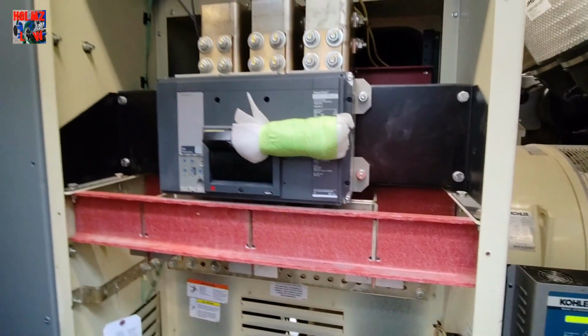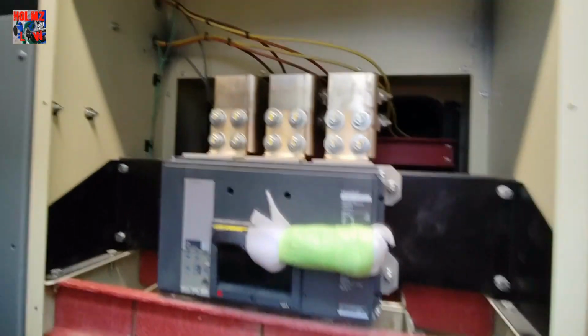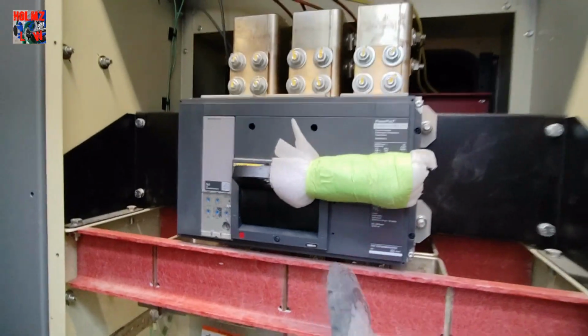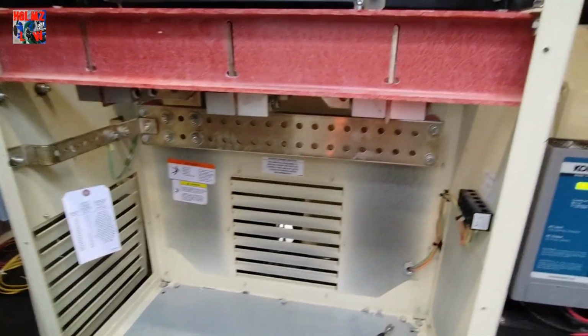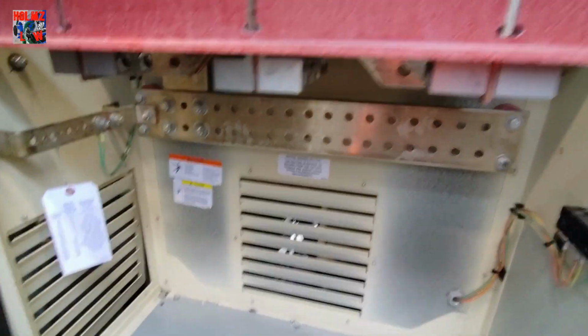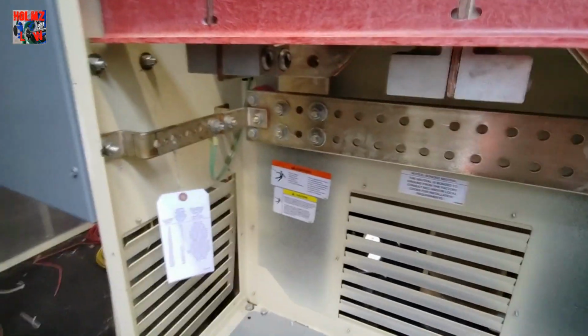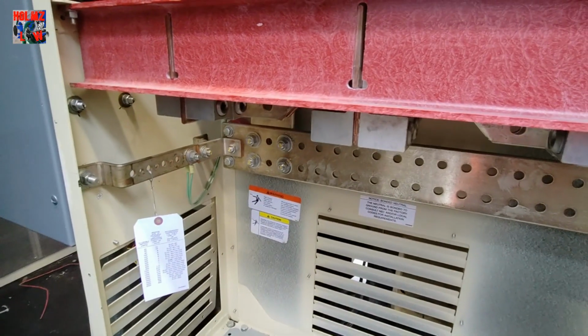And so basically, this is what I want to show you. This is the first means of disconnect for the actual generator. This here would be the first disconnect. It's a 1600 amp disconnect. This is the first disconnect before they actually start feeding. If you wanted to shut the generator down and not feed anything, this would be the main breaker for that.